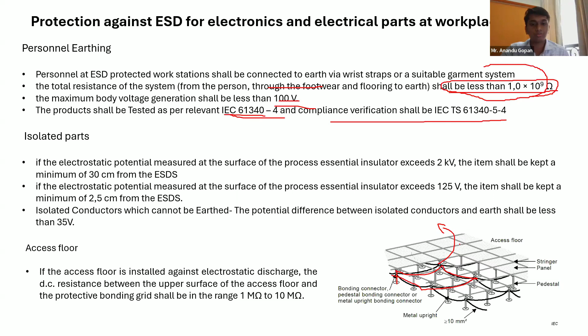If you are having an access floor, especially to control electrostatic discharge, their minimum insulation resistance must be 1 mega ohm to your protective bonding network - generally between 1 mega ohm to 10 mega ohms. So this is all for electrostatic discharge.